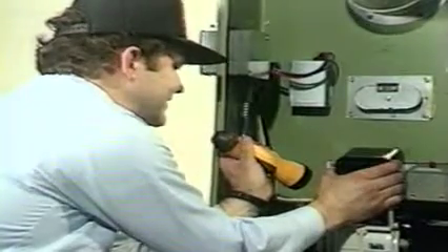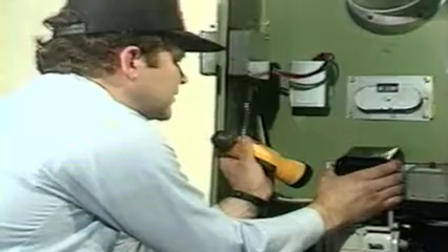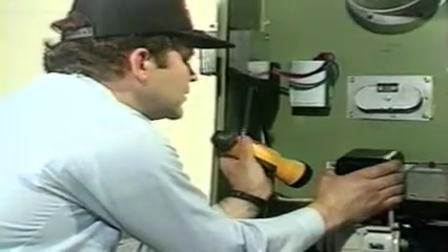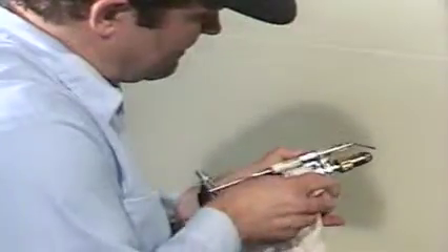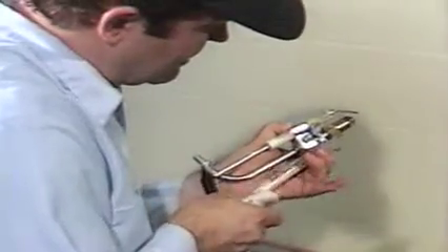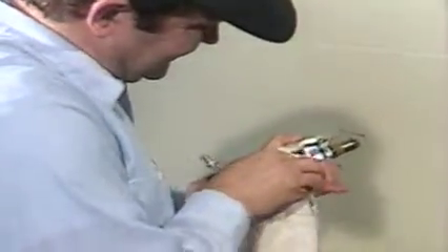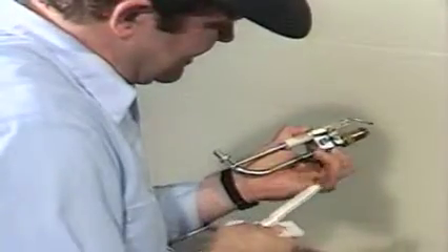Start with the contact between the electrodes and the transformer springs. There should be no arcing here. Check the gap setting on the electrodes to be sure it's set to the manufacturer's specifications. A bad setting can cause loss of ignition, which in turn leads to safety lockout. Inspect the electrodes for cracks, carbon residue, moisture, and pinhole leaks. Any leaks can cause faulty ignition. Replace any electrodes with worn tips or that look questionable. Usually a complete electrode assembly is recommended.